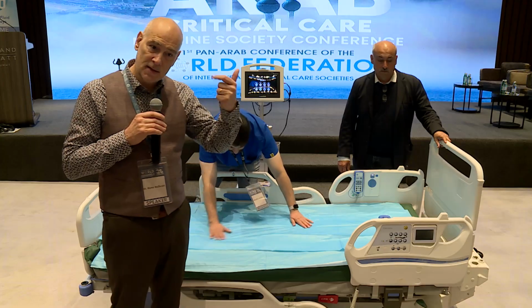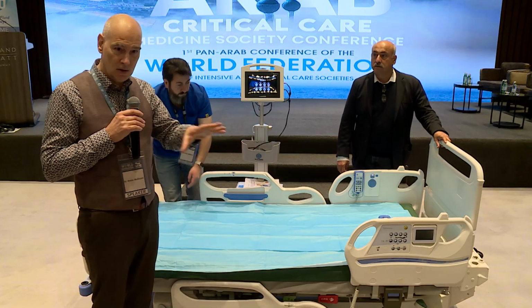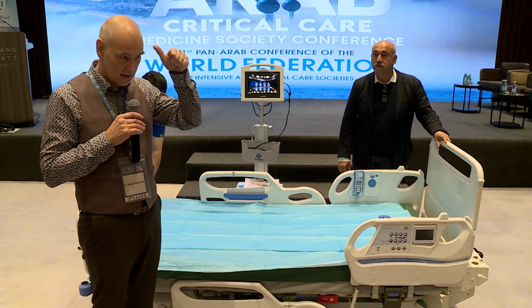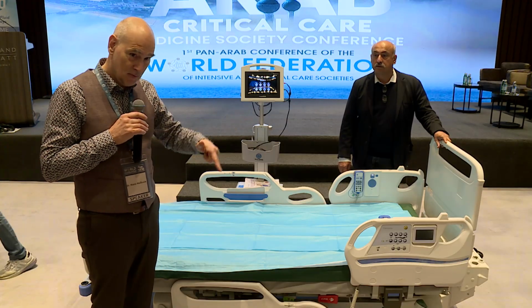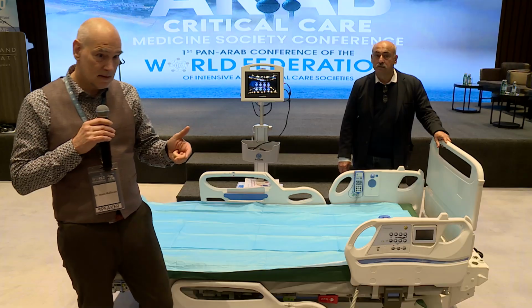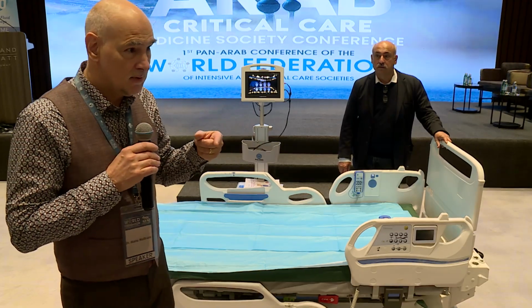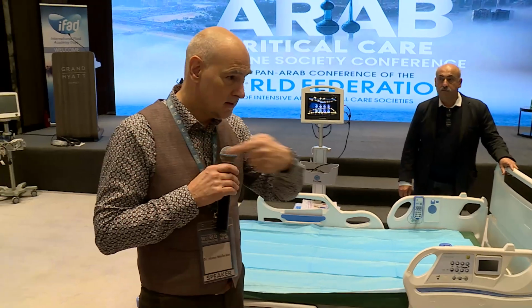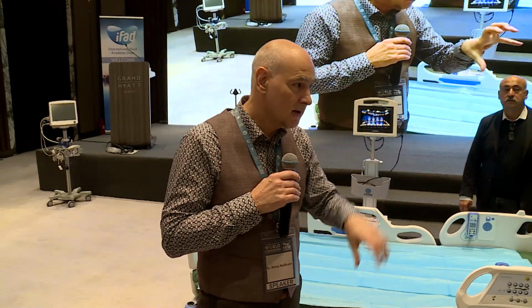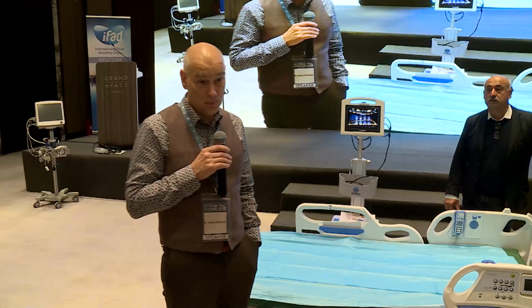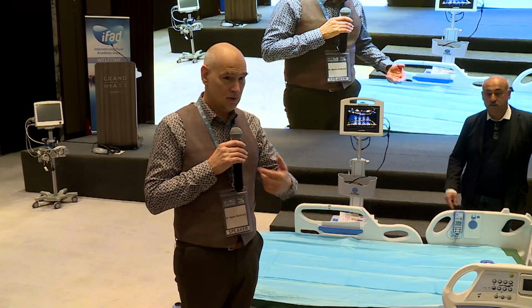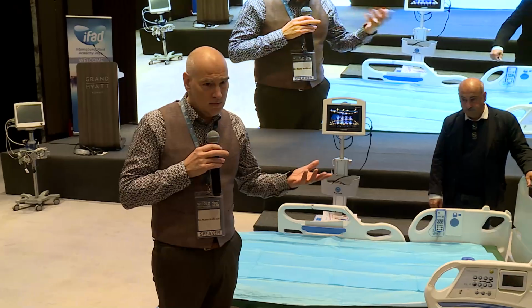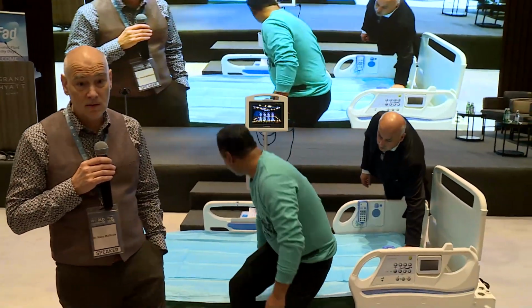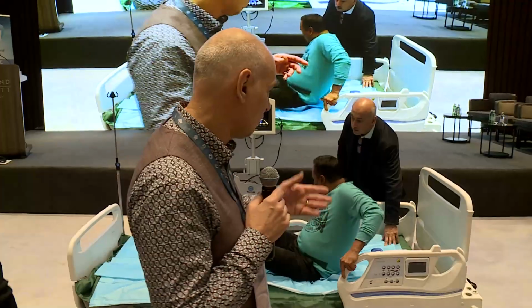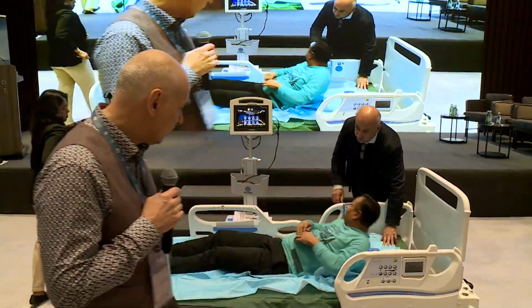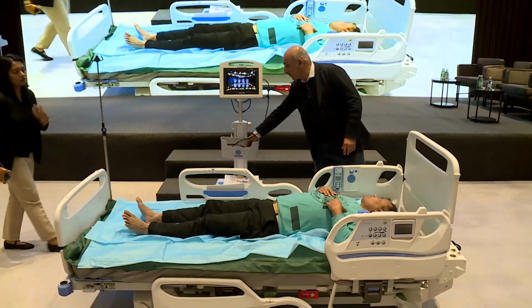So if you want to use a device, these are the things that you need to ask the company whether the device has multi-frequency, 8 electrodes, so both sides, segmental analysis, and a kind of repetitive measurement on the left, on the right, crossing the arms, the legs, and having a robust mean value that is reproducible. Because otherwise, if you only do it left, only right, you change a bit on the electrodes, you will find different results between nurses, and the intra and inter-observer variability is too great. So this is okay, and we will now show you how to do it.